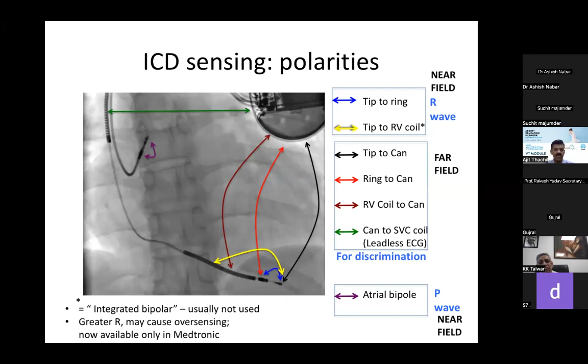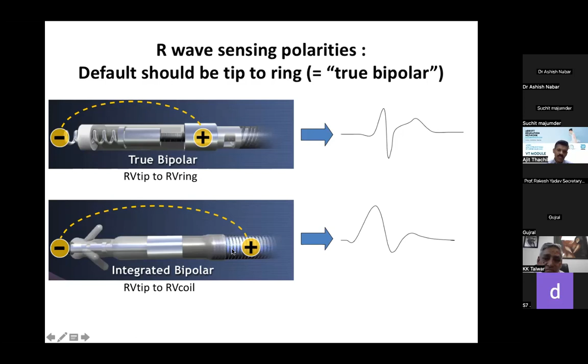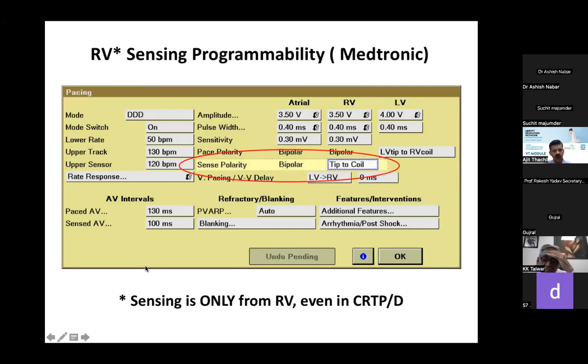Now, how are these sensing polarities configured? This is the true bipolar, which should always be used. There is also an option of the integrated bipolar, which will give a larger R wave, but is generally not recommended. You can change it in Medtronic devices. But what is more important, a very basic thing, is that sensing is always from the right ventricle. Even if it's a CRTP or a CRTD, sensing is always from the right ventricle.